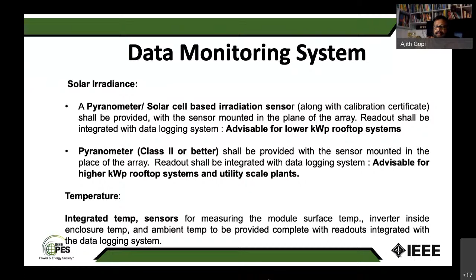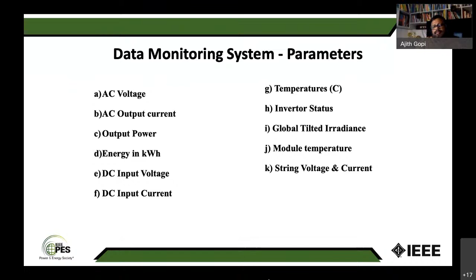There will be integrated temperature sensors as well. Generally, we monitor this data: AC voltage, AC current, output power, energy in kilowatt hour, DC input voltage, DC input current, inverter status. Global tilted irradiation is recorded for performance ratio calculations, module temperature, string voltage and current. But these are all the basic status parameters that we are measuring.